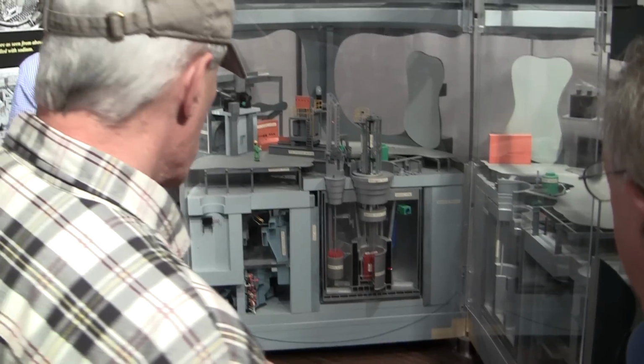I got that. Yeah. So this loss of heat sink test would be turning off the power to the secondary, so you're not drawing the heat out of the core. You would shut down the tertiary, the water system. The tertiary, okay. And so this other one, the loss of flow test, is that shutting down the intermediate? The loss of flow test is shutting off the pump, just turning off the primary pump, the pump for the primary sodium. So these two tests are turning off the primary and turning off the tertiary.